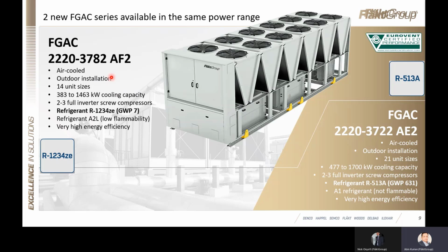The same chillers are available with R513A. R513A has a lower GWP of 631 and it is classified as an A1 class refrigerant. So it's a non-flammable gas and no additional precautions are required for the installations. And these are available from 477 to 1700 kilowatts in cooling capacity and available in 21 frame sizes.